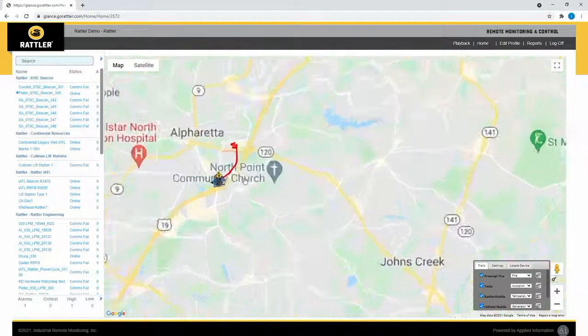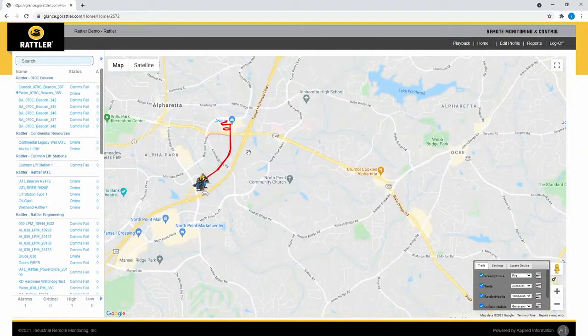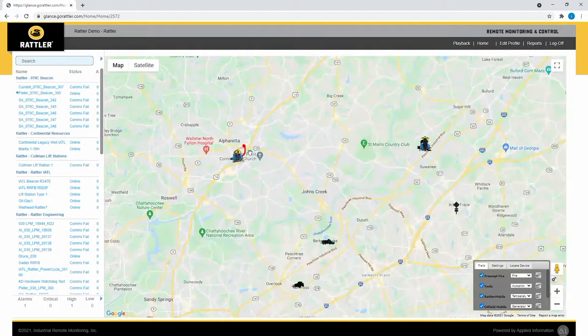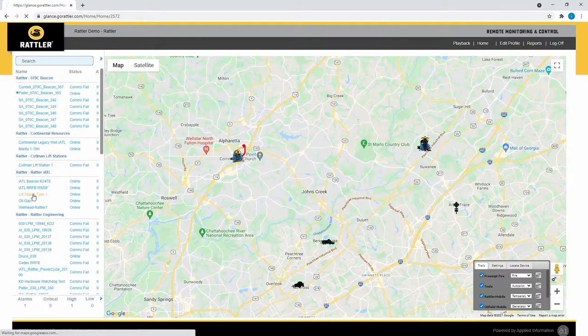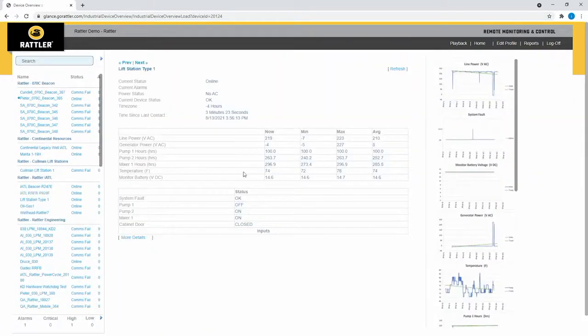You can log on, and it presents you with a map, and what you can see is some trails by mobile devices and things like that. But what we're going to do is look down here, and we saw that the lift station was on this list. This gives you an indication that it's not an alarm, and it gives you all the parameters of this lift station: the AC voltage, the generator power and so forth, the temperature, and all the status of the pumps.